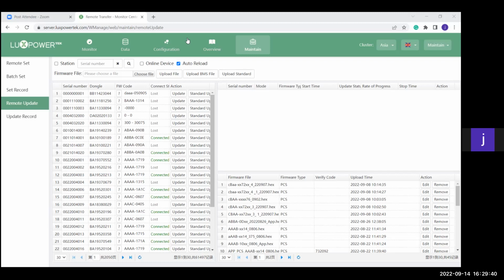On the bottom of our machines, we have 2 switches. We have an EPS power switch, that means that switches on the EPS. And we have a physical power switch on these inverters. Now, on this inverter, it's important to have both of the switches on when you do an update. If the EPS switch is off, the update will fail. You can't update the machine when the EPS switch is off, or Eskom is not there, or PV power is not there. One of the 2 must be there for your updates to complete.